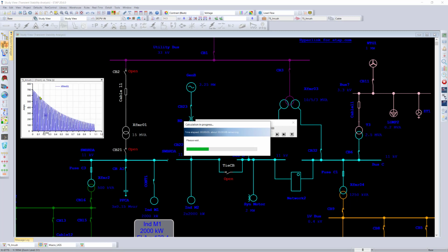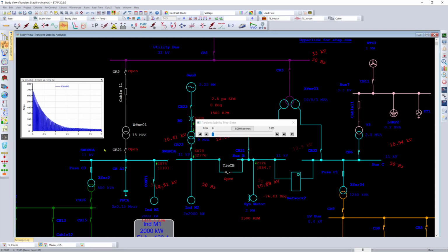And we can see the actual inrush current pulsating as the magnetization of the transformer dies off, and we are essentially reaching a steady state value. But this value is essentially pulsating and makes it quite difficult to understand the starting point, the peak current, the inrush value, the inrush duration, and so on. And that's one of the key deliverables for grid code compliance.